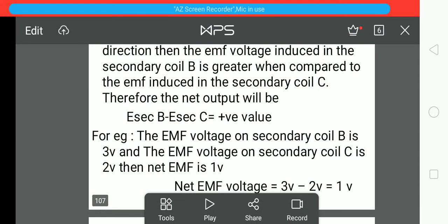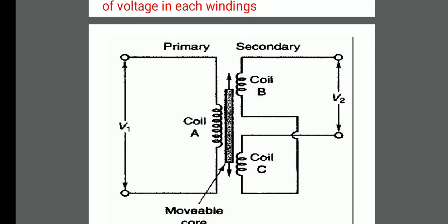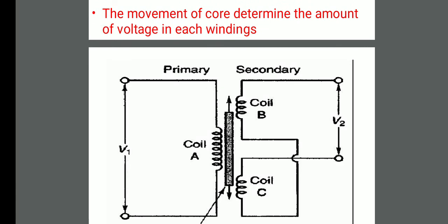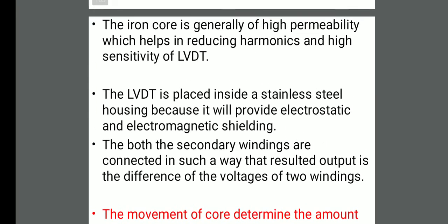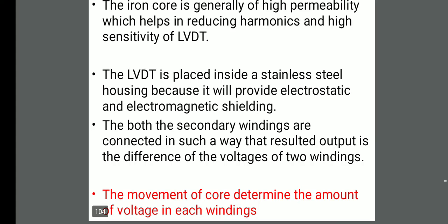One more important thing to note is that the entire assembly of the LVDT is contained in a steel casing in order to prevent any losses and to ensure accurate readings. The entire LVDT is enclosed in a stainless steel housing because it provides electrostatic and electromagnetic shielding. Electromagnetic or electrostatic effects can give wrong readings, so in order to prevent that, the entire assembly is placed inside a stainless steel housing.